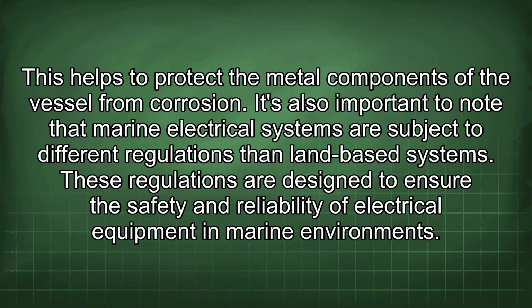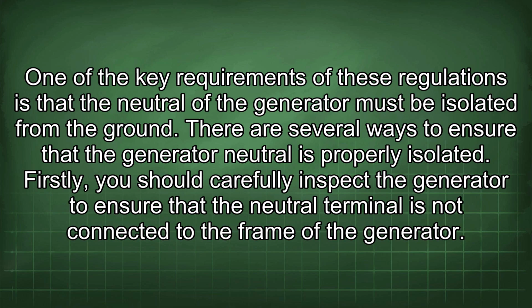It's also important to note that marine electrical systems are subject to different regulations than land-based systems. These regulations are designed to ensure the safety and reliability of electrical equipment in marine environments. One of the key requirements of these regulations is that the neutral of the generator must be isolated from the ground. There are several ways to ensure that the generator neutral is properly isolated.